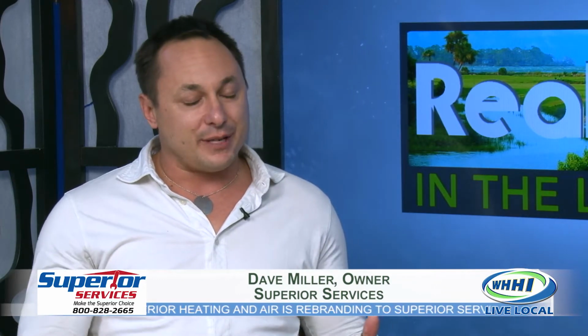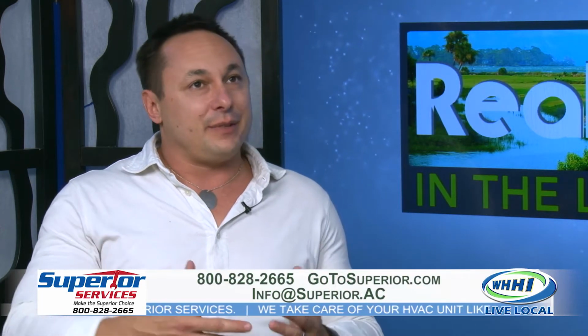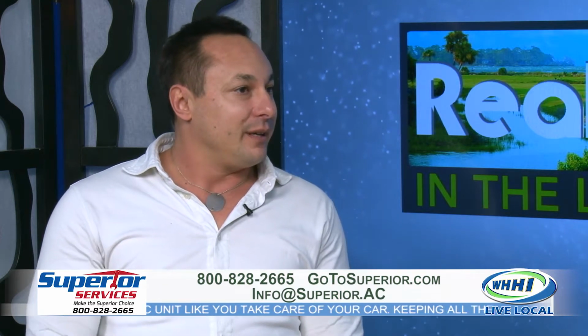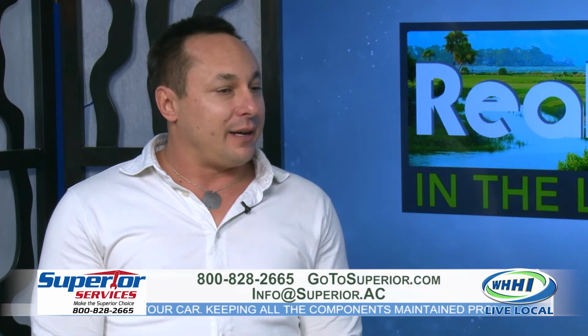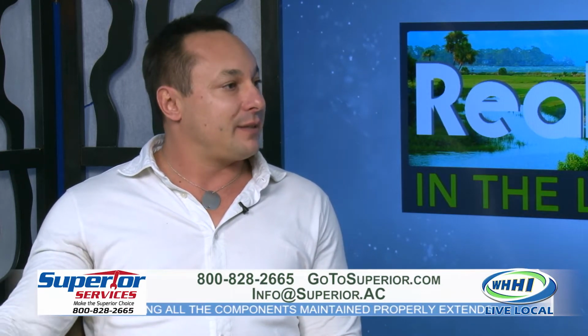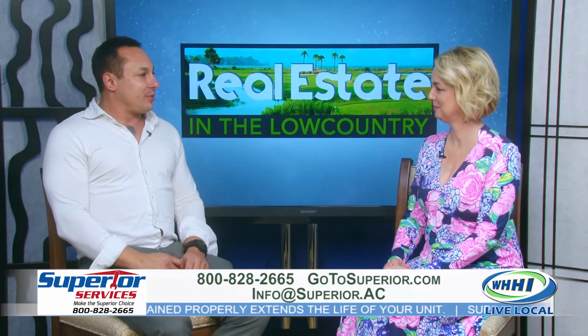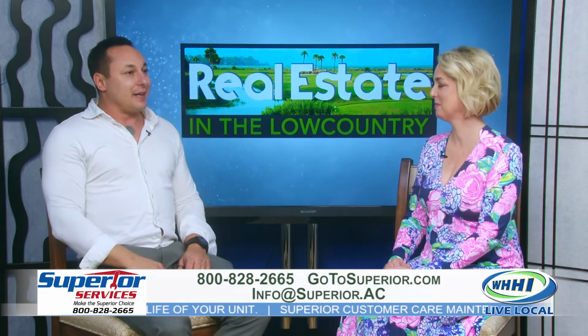What we've noticed is a lot of our customers, or people in general, have hot and cold spots or an uncomfortable place in their house, and they feel like they just have to deal with it. Oh well, I'll have to bundle up if I go into that room. We're trying to educate everybody that it doesn't have to be that way. You should only have a couple degrees variance from one room to the other, and if there is more than that, then have it checked out. There's a host of reasons, but it could be as simple as a dirty air filter slowing the airflow down to the house.